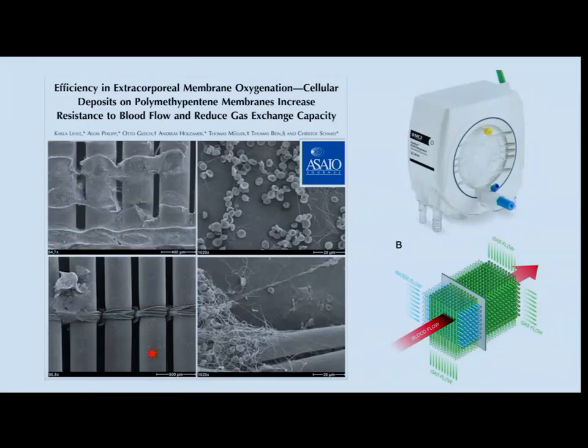They can also electrospin them on large surfaces. These are on the wider end of things, about 200 to 300 microns wide, but you have fibers now around 180 microns. As you can see, the resistance to get blood through this gap is going to be super high. That's why you need to pump it really strongly, especially with the thick blood, with all that viscosity.